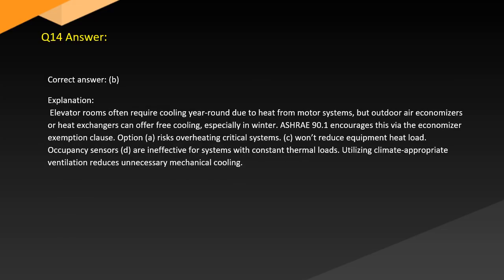Answer. Correct answer: B. Explanation. Elevator rooms often require cooling year-round due to heat from motor systems, but outdoor air economizers or heat exchangers can offer free cooling, especially in winter. ASHRAE 90.1 encourages this via the economizer exemption clause.